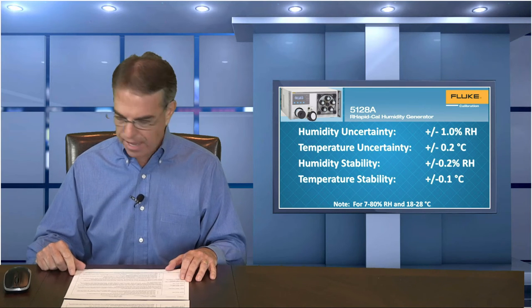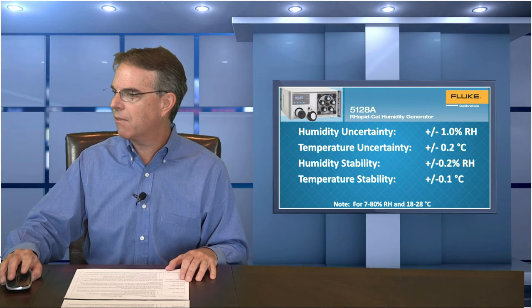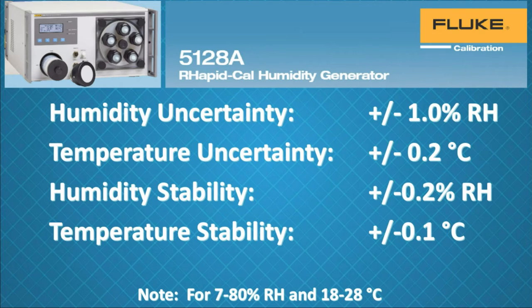So thanks to Greg for taking the time out of the show to be on Calibration TV. Here are some more detailed specifications on the 5128A. Humidity uncertainty is plus or minus 1%, over the bulk of the range of the calibrator from 7 to 80% RH. Up in the higher areas, from 80 to 95%, the number goes up to 1.25% RH accuracy uncertainty, but still a very good number. Temperature uncertainty is plus or minus 0.2 degrees. And importantly, with a calibrator like this, you need good stability of temperature and humidity as well: plus or minus 0.2% RH stability and temperature stability of 0.1 degrees. Very good specifications.